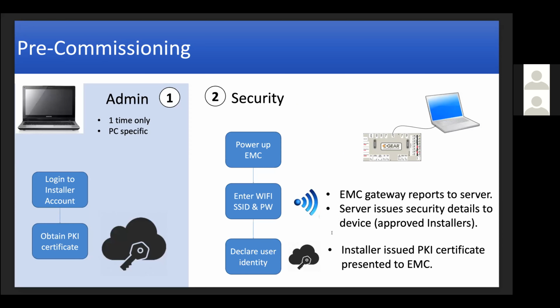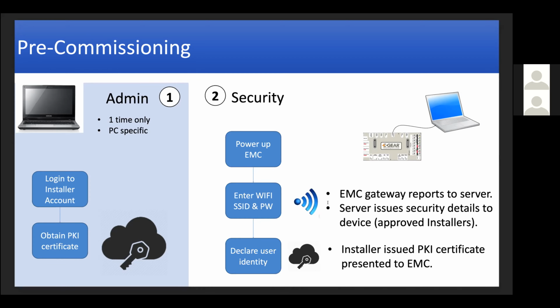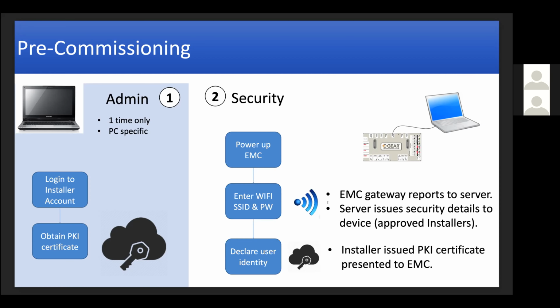So pre-commissioning is administrative, first time only, and it's specific to that device, as I was just mentioning. You would log into your installer account and you would get that PKI certificate and load it onto the laptop. Once that's done, then that laptop is ready to commission your battery system. Once you've got the EMC, the energy management system, powered on, you would enter the Wi-Fi SSID and password if you're not using wired Ethernet.